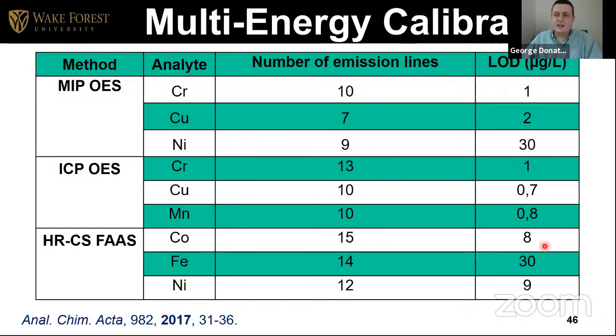Here are the LODs. One thing I need to mention, the LODs are usually a little higher than the traditional methods for multi-energy calibration, because you are using some emission line that is not very sensitive, and that messes up the sensitivity a little bit. But again, the method is not too different in terms of limit of detection from the traditional method, a little worse. And the whole goal here is to improve accuracy rather than improving the LOD.